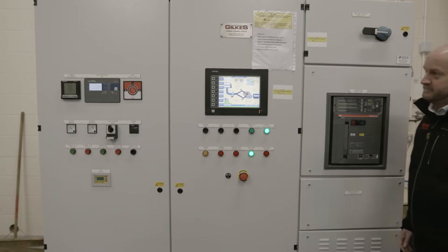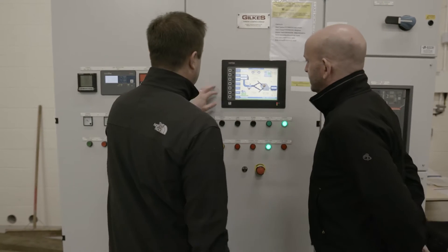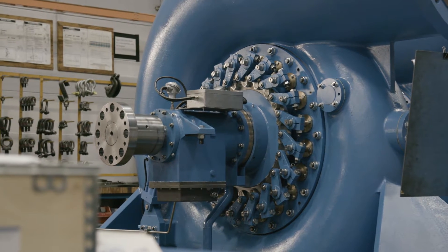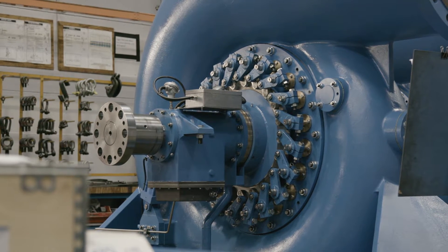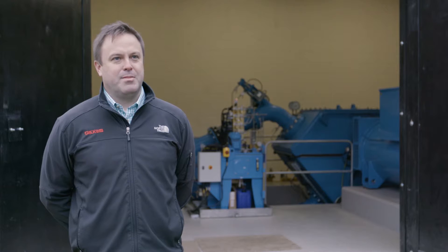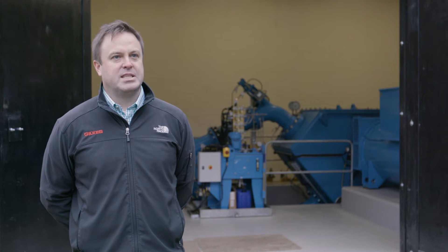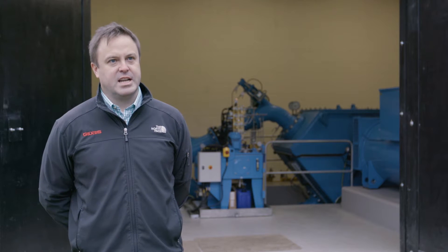The theory behind hydropower is that we ultimately harness the energy available in the water — both in terms of the pressure and the flow rate or movement of the water. Turbines fall into two categories: reaction and impulse. In a reaction turbine the runner is fully submerged and it harnesses the energy of the water passing through the runner, both in terms of its pressure and the kinetic energy available.